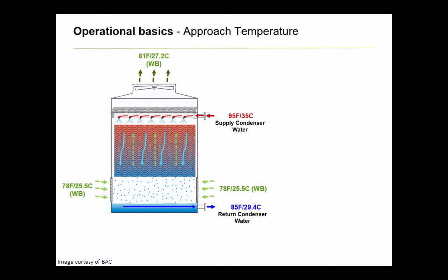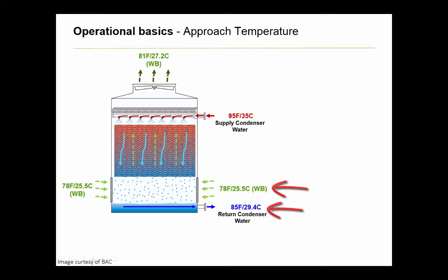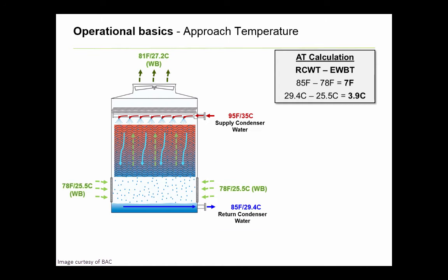As a side note, when talking cooling tower basics, the term commonly used is the approach temperature. This is the difference between the ambient wet bulb temperature entering the tower and the cooler water leaving the tower and being sent back to the building. The term approach is used because the tower's purpose is to return water that's as close as possible to, or approaching, the incoming air wet bulb temperature. On average, this design value will hover around 7 degrees Fahrenheit, or 3.9 Celsius, as you can see from the math shown.